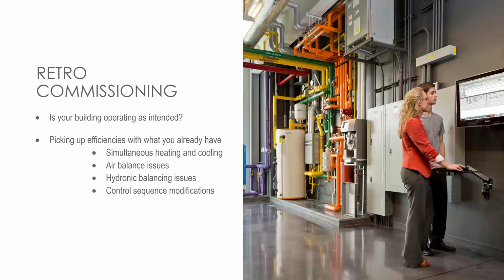Building automation systems sometimes act erroneously for a variety of reasons. Maybe the new guy forgot to put the pump back to auto after having it in hand for maintenance, and it's been running all year. Something as simple as that, or maybe it's just the BAS system throwing errors from a software standpoint. Occasionally doing a retro commissioning to make sure your building is operating as intended is critical.